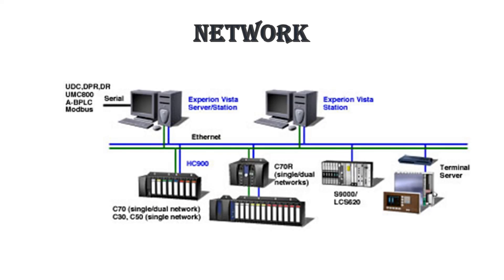The process control network is the backbone on which the entire DCS is connected. The network runs across the plant, connecting all intelligent devices in a reliable, deterministic manner. Process control networks, also called PCNs, can use open protocols such as Ethernet or can be proprietary. PCNs are generally installed in a redundant manner to improve reliability and are installed away from regular power cables to reduce the impact of electromagnetic interference, thereby increasing the reliability of the overall system.